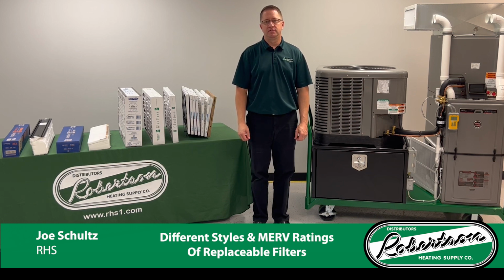First, I would like to discuss what Merv stands for, which is Minimum Efficiency Reporting Value. The value ranges from 1 through 20, and the higher the Merv rating, the smaller the particle the filter will capture. Merv ratings of 1 through 4 filter down particle sizes of 10 microns. Pollen, dust mites, carpet fibers, for example. Applications include residential, window ACs, and commercial.